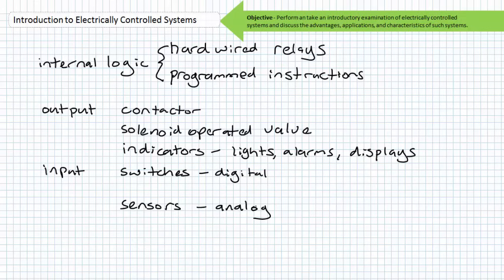An operator turns a system on or off. A pressure switch tells the system pressure is above or below a certain set point. A sensor, in contrast to a switch, measures some quantity and produces an electrical output proportional to the magnitude of the quantity being measured. Switches could be considered sensors. However, I'm using the term sensor to suggest a sensor not only detects the presence or absence of a condition, it also measures and quantifies it.